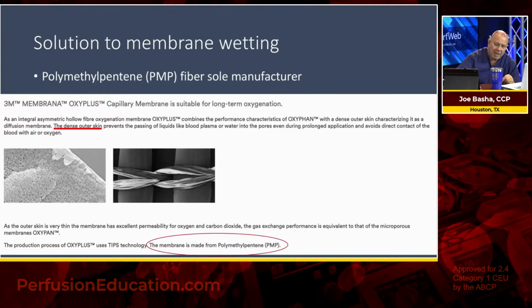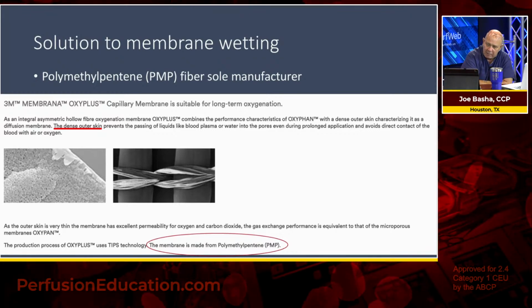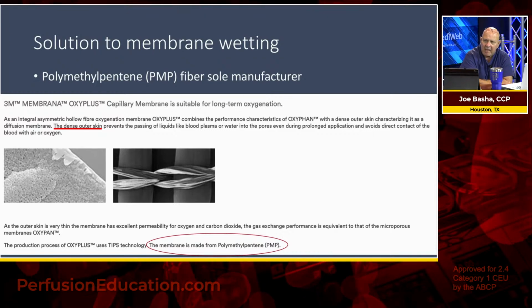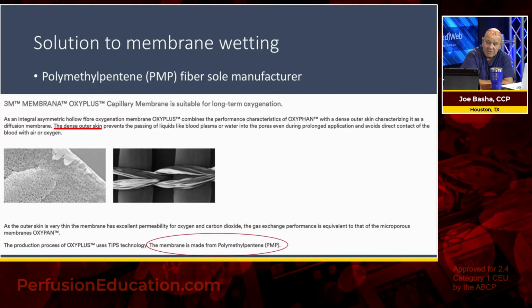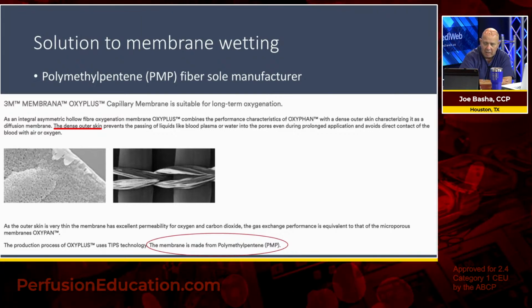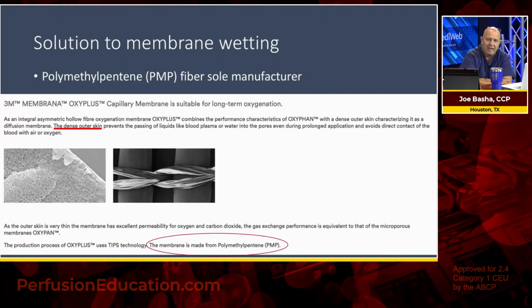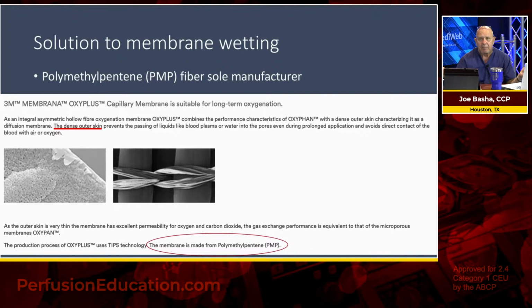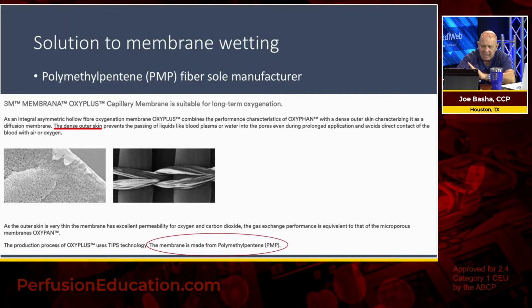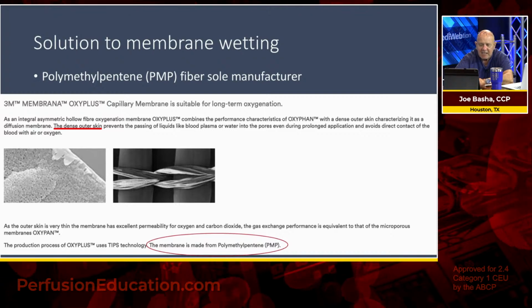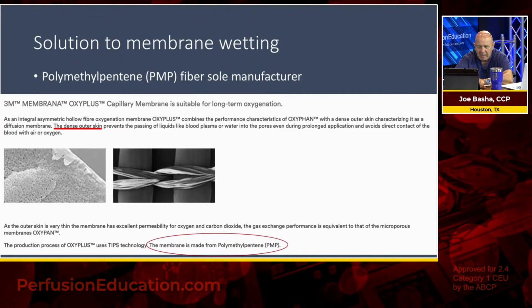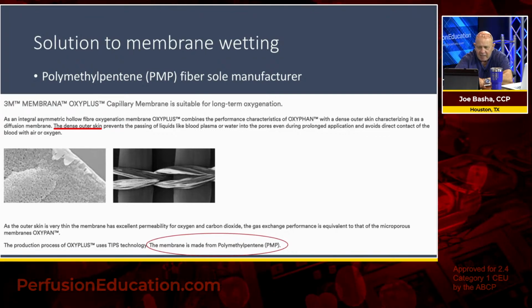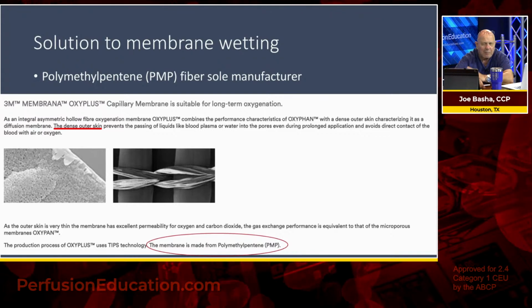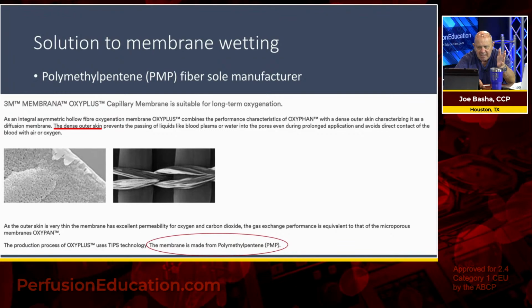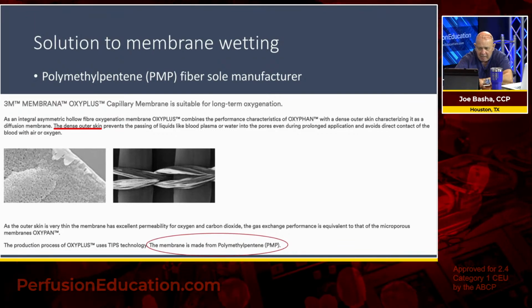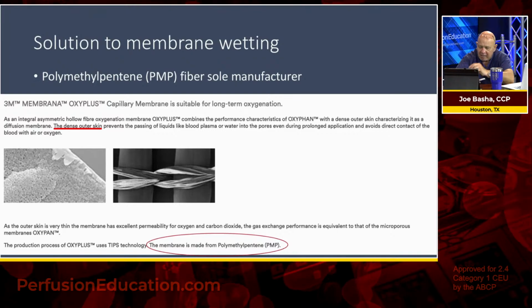Now, a microporous hollow fiber membrane oxygenator of polypropylene design is a diffusion gas transfer device also. So this is a little bit of marketing going on here. You really don't have a direct gas to blood interface like you would in a bubble oxygenator, for example. As the outer skin is very thin, the membrane has excellent permeability for oxygen and carbon dioxide. The gas exchange performance is equivalent to that of the microporous membrane's OXYPHAN, which is the polypropylene version. And the membrane is made of, of course, PMP.